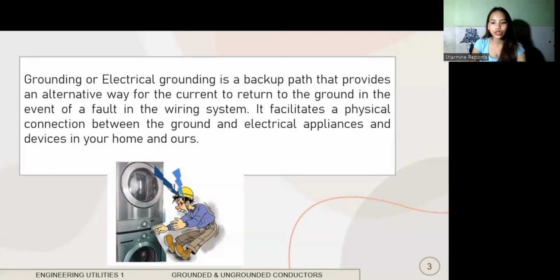And take note that grounding is a backup pathway that is only used if there is a fault in the wiring system. If there is no problem or fault in the circuit, it is not needed, because we have the original conductors in the circuit, and they take care of the electric current from the source to some appliances and back to the ground or source, creating a cycle. So that is the meaning and the purpose of grounding.